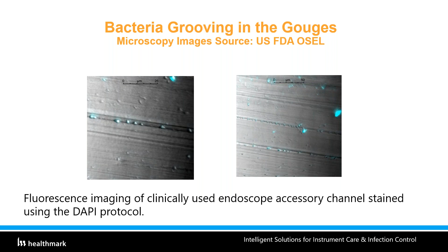And here, for example, you see a damaged ureteroscope. So part of it is to have it on hand for incoming inspection, but moreover to use it as you go forward. So here, if you have a really high magnification, this was a patient-used scope. Although you couldn't see those with a borescope, when you magnify these to micrometer, you can actually see that. So when they use that DAPI protocol, you put these in and then you run it under the light, you see all these popping up. So even a scope that looks good, you possibly have grooves in it. The reason being the potential for the instrument that you put in, or sometimes even a brush that has a sharp tip, that could damage the inside of the endoscope.